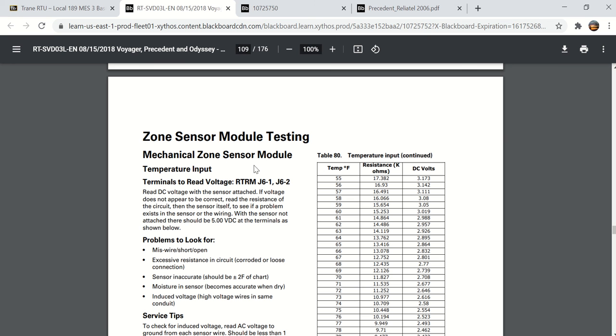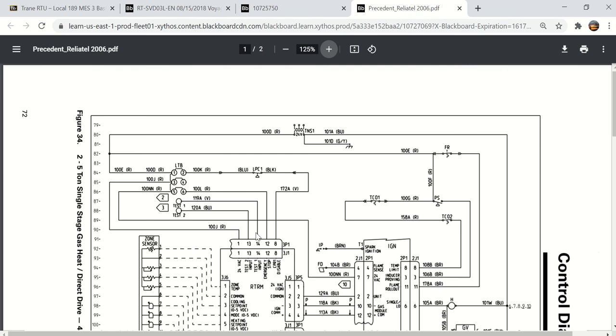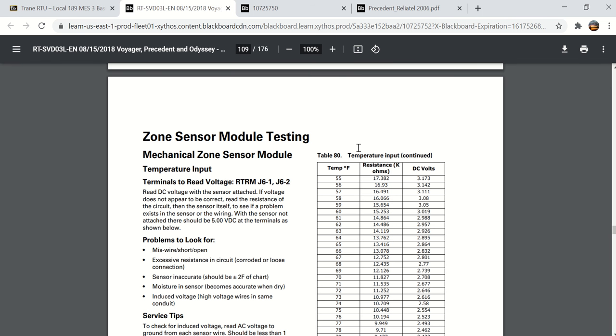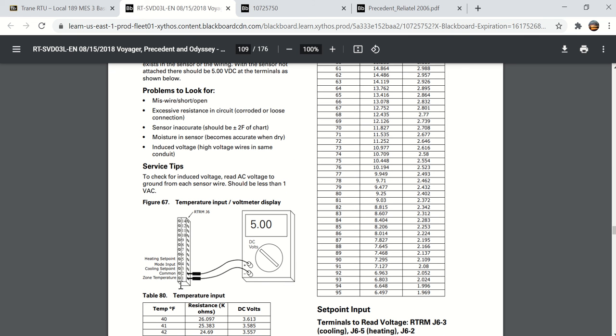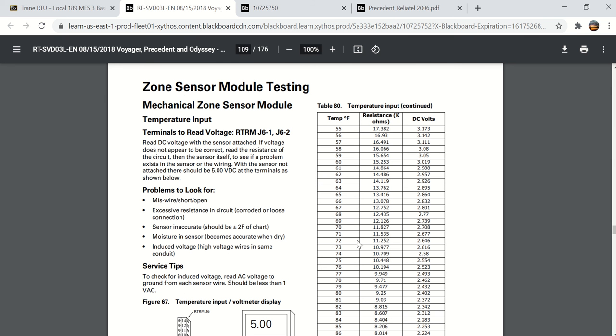Start out here on page 109, and if you're using the Trane zone sensor module for temperature input, and if you remember, we just looked at the RTRM board J6 1 and 2 right here. Here was J6 1 and 2, that was zone temperature and common. So on this manual here, it tells you that if you were to read the voltage between RTRM J6 1 and 2, you could actually, right here, read the zone temperature to common with a DC voltmeter. If the actual room temperature was 72 degrees, the voltage you would read would be 2.64 volts.